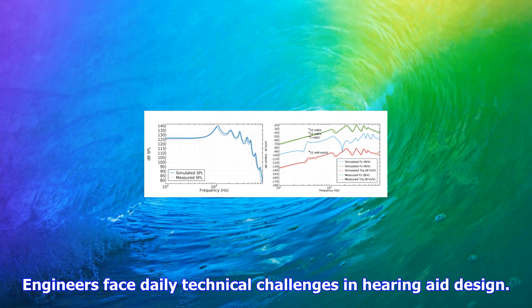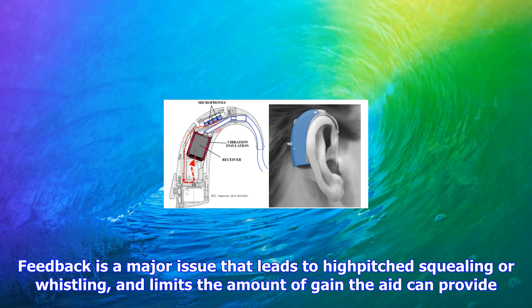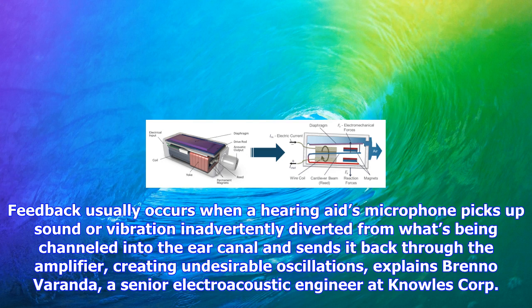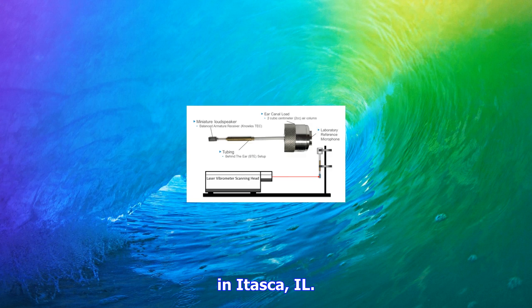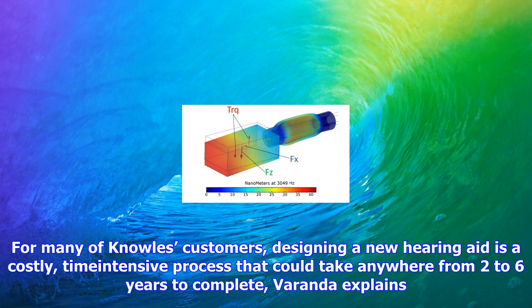Feedback is a major issue that leads to high-pitched squealing or whistling, and limits the amount of gain the aid can provide. Feedback usually occurs when a hearing aid's microphone picks up sound or vibration inadvertently diverted from what's being channeled into the ear canal and sends it back through the amplifier, creating undesirable oscillations, explains Brenno Veranda, a senior electroacoustic engineer at Knowles Corp. in Itasca, IL. For many of Knowles' customers, designing a new hearing aid is a costly, time-intensive process that could take anywhere from 2 to 6 years to complete, Veranda explains.